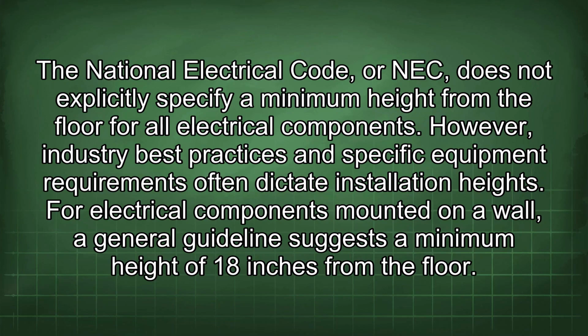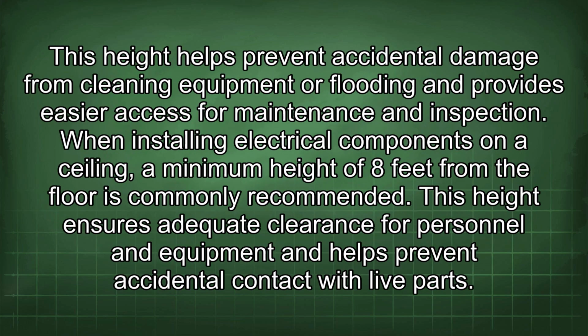The National Electrical Code, or NEC, does not explicitly specify a minimum height from the floor for all electrical components. However, industry best practices and specific equipment requirements often dictate installation heights. For electrical components mounted on a wall, a general guideline suggests a minimum height of 18 inches from the floor. This height helps prevent accidental damage from cleaning equipment or flooding and provides easier access for maintenance and inspection.